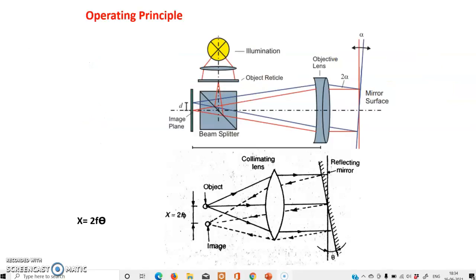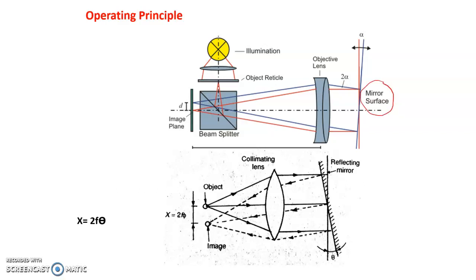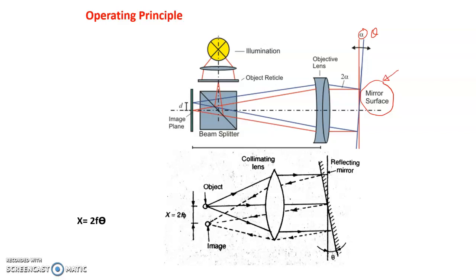The operating principle of the autocollimator can be explained in two parts. The first part is without any deflection to the mirror surface, and the second part is with a deflection of an angle theta on the mirror surface. Let us consider the first part, where the mirror does not have any deflection — it is purely vertical — and that condition is shown with the red color beams.